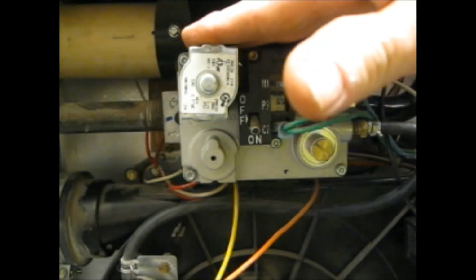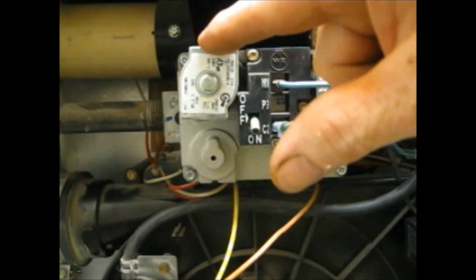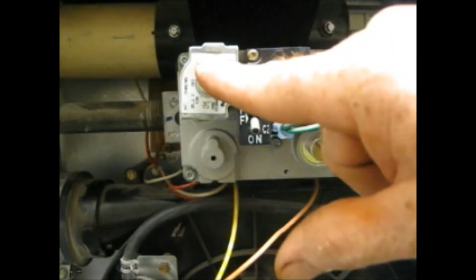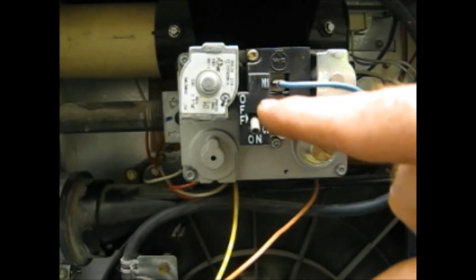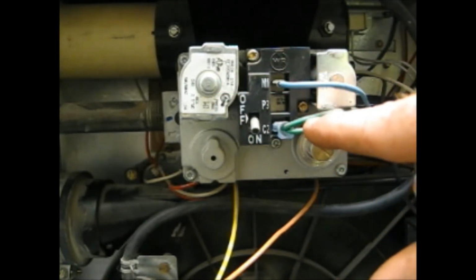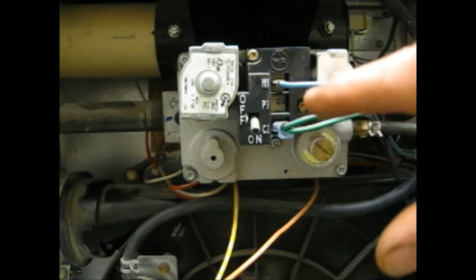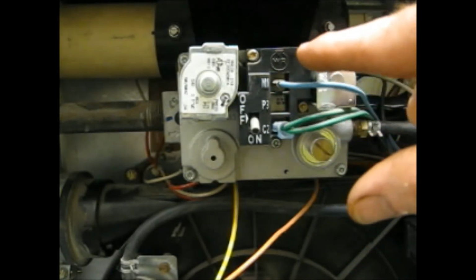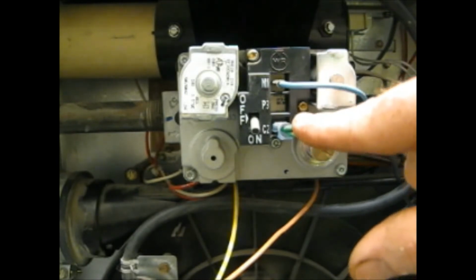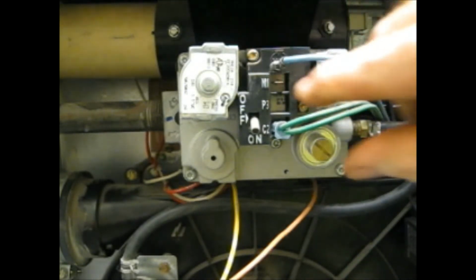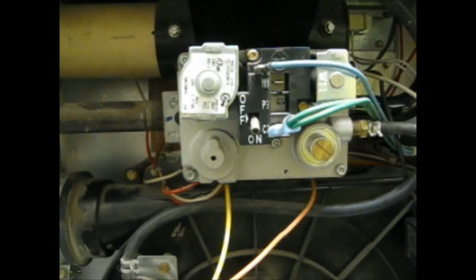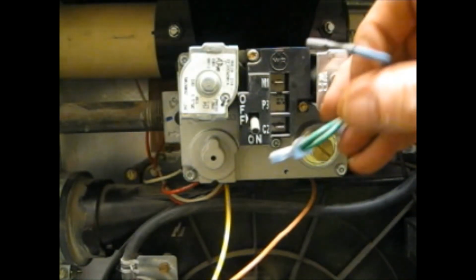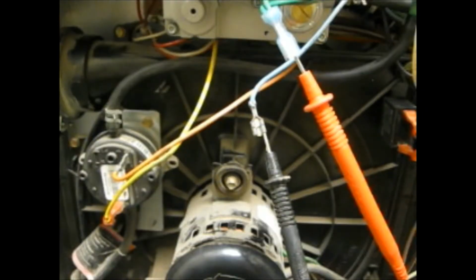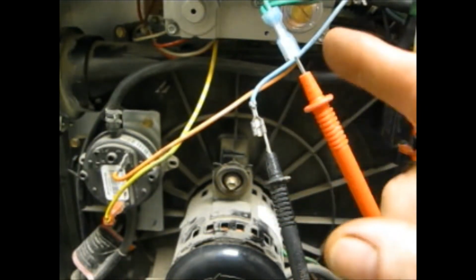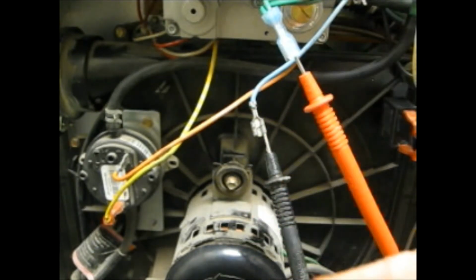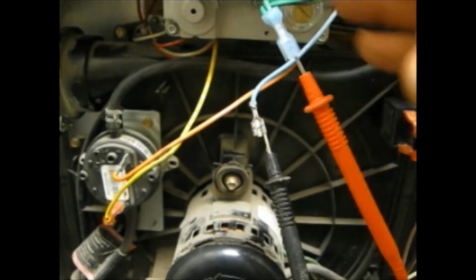Now, if you were to hold your hand on this, you'll actually hear the solenoids click to open up the valves. So that's one telltale sign to look for. But another thing we can do, just to make sure you don't have a problem with your circuit board, we can also test for voltage at M1 and C2 here. So we're going to go ahead and disconnect these. And just like we did before, we're going to attach our voltmeter to these two leads. Okay, our leads are connected to the gas valve, and we're just waiting for that 90 seconds for everything to go through its sequence.